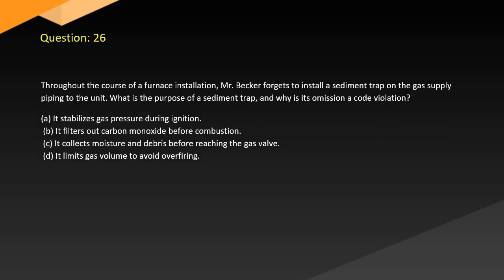Question 26. Throughout the course of a furnace installation, Mr. Becker forgets to install a sediment trap on the gas supply piping to the unit. What is the purpose of a sediment trap and why is its omission a code violation? A. It stabilizes gas pressure during ignition. B. It filters out carbon monoxide before combustion. C. It collects moisture and debris before reaching the gas valve. D. It limits gas volume to avoid overfiring.